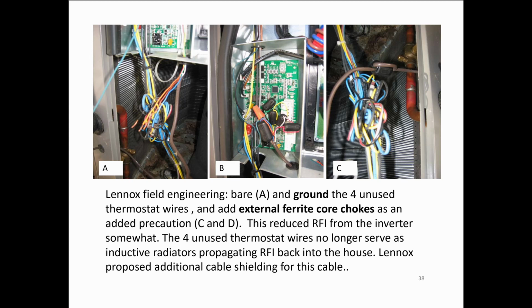And I was sitting watching the scope on my IC-7300, and that didn't cause very much change. When he added a ferrite choke to the cable, that's the brown cable here, you can see the ferrite choke with 1 turn. That seemed to reduce the RFI considerably. But there was still some interference, and Lennox proposed somewhat vaguely, the field engineer said, well, I could put insulation over the entire thermostat line, or I could try insulating the entire power line going to the compressor.